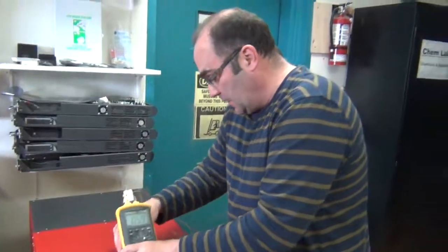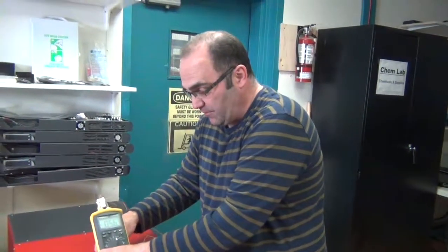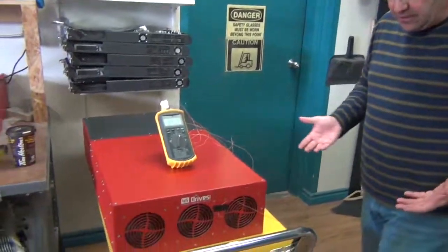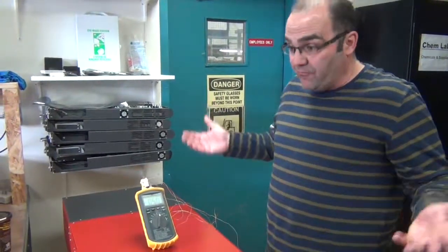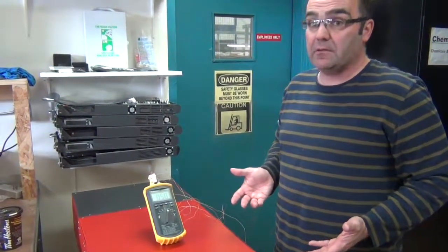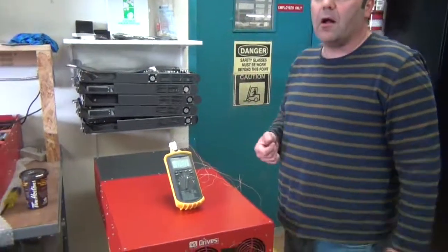In a warm room, which is 25 or 75 degrees, we get an increase of about roughly 10 degrees Fahrenheit inside the unit to the external temperatures. This would be far warmer than most server rooms, but as you can see thermally, this thing cools very well.